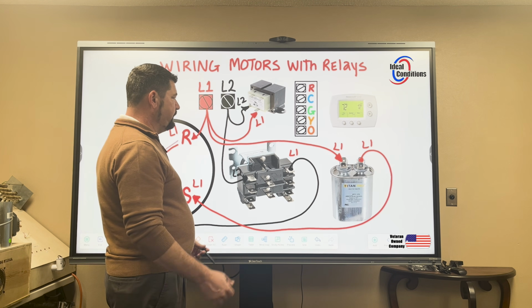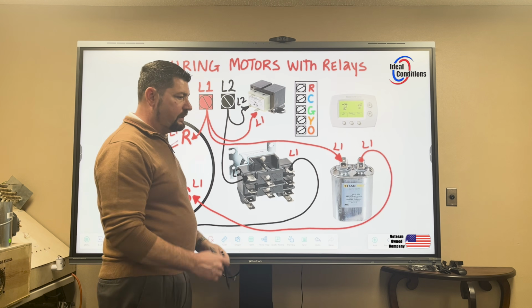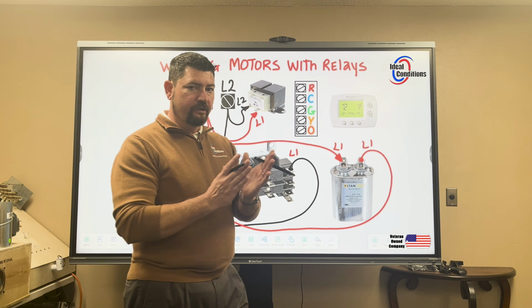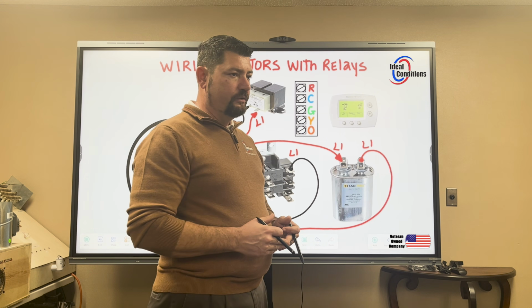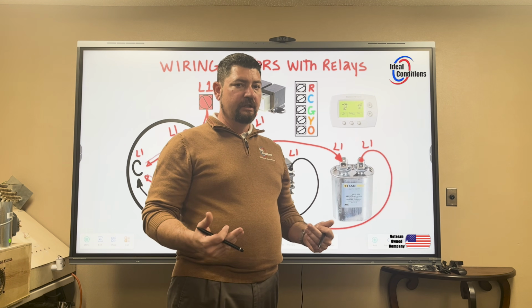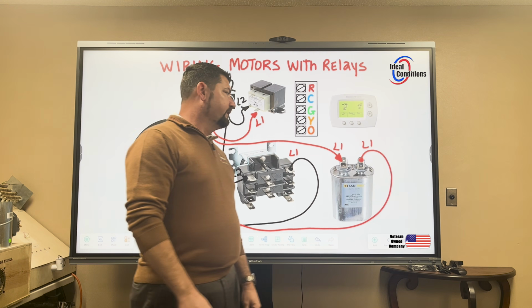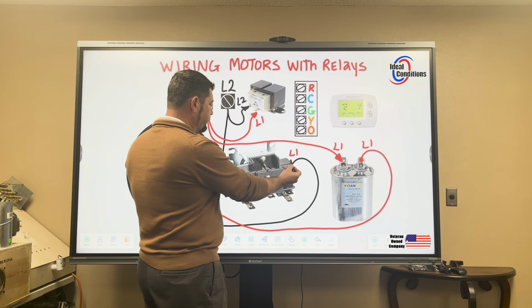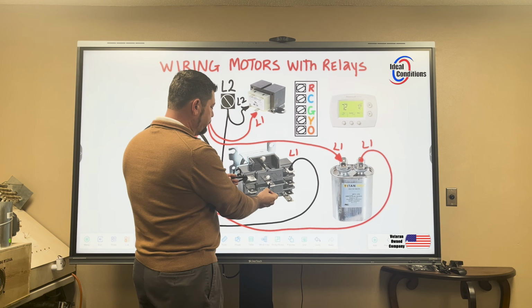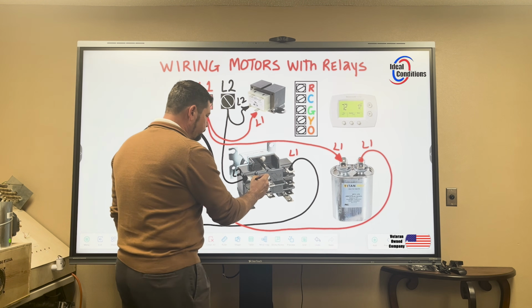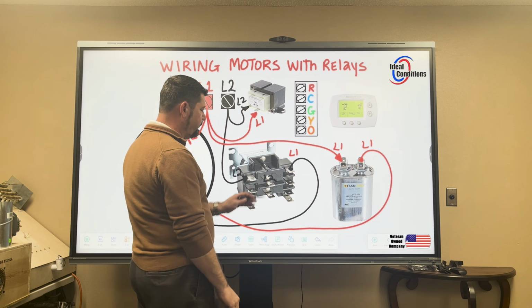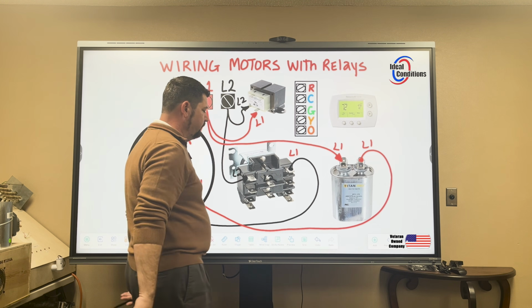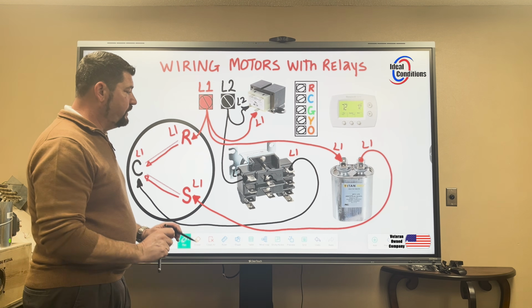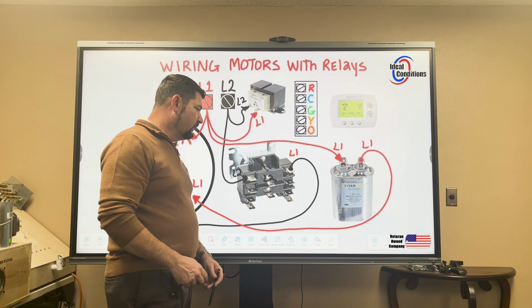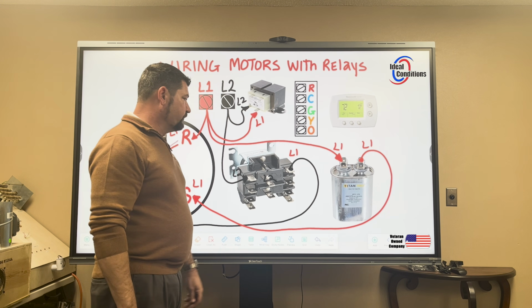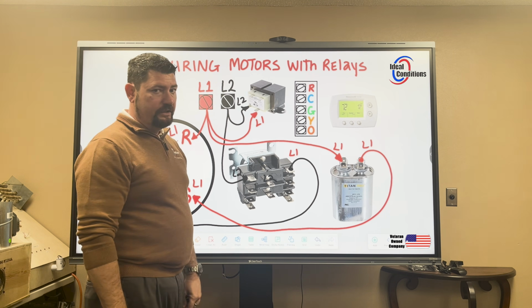There are only 2 voltages we can read in a 240 application when we're trying to find out if something is open or closed. If it is closed, you will read 0 volts. If it is open, you will read 2 legs. Here it's open, we're reading 2 legs. Here it's closed, we're reading 0 because L2 is present here. So even if I went from here to here, I will still read 240. Understanding our path of electricity is very important. That's why these videos are very special for me to put out, so I can better help illustrate this on this very expensive technology that we have here.